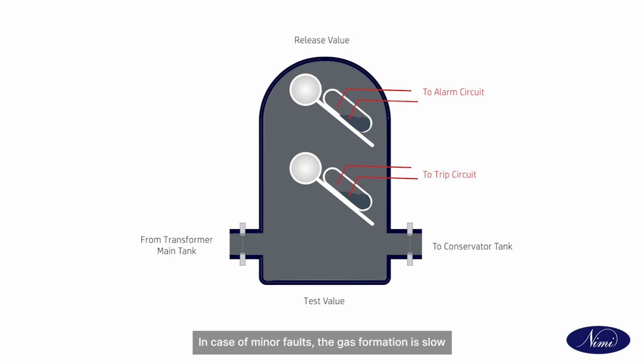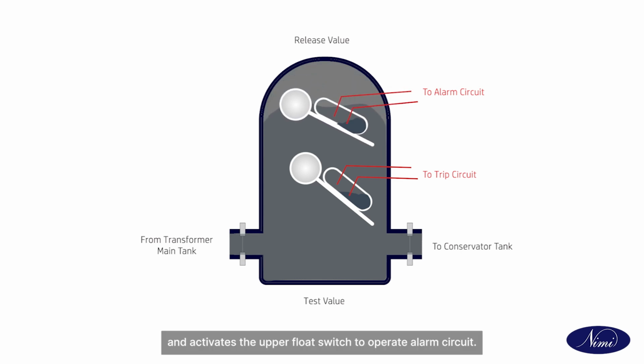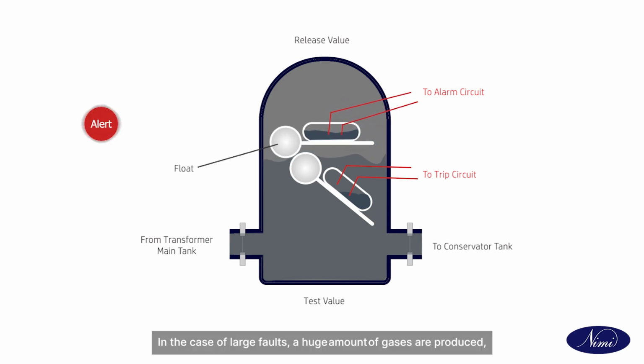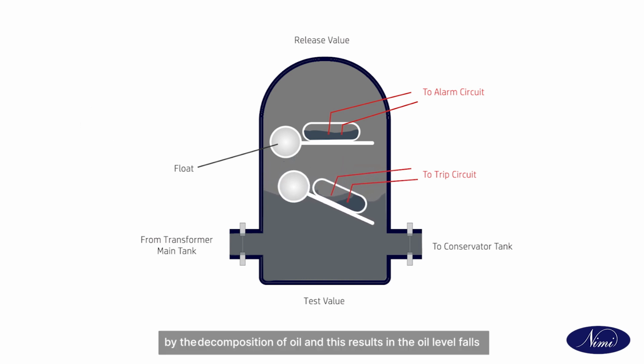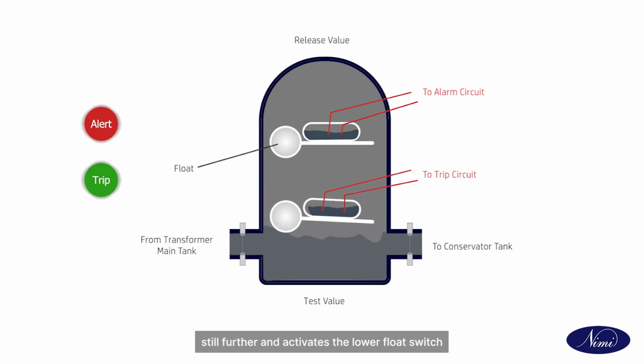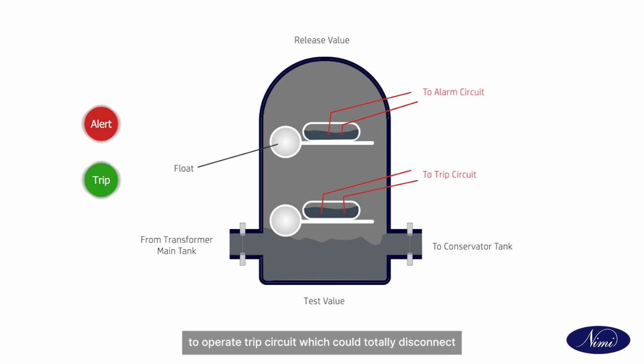In case of minor faults, the gas formation is slow and will accumulate in the upper part of the Buchholz container, which causes a fall of the oil level in it and activates the upper float switch to operate the alarm circuit. In the case of large faults, a huge amount of gases are produced by the decomposition of oil, and this results in the oil level falling still further and activates the lower float switch to operate the trip circuit, which could totally disconnect the transformer from the main supply.